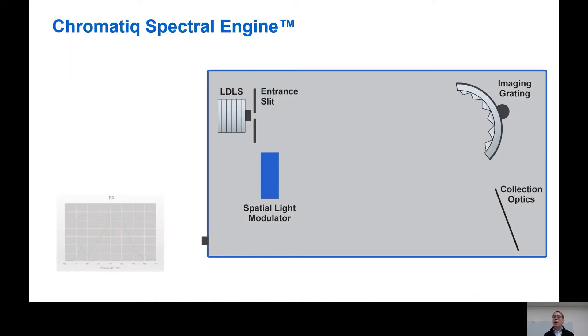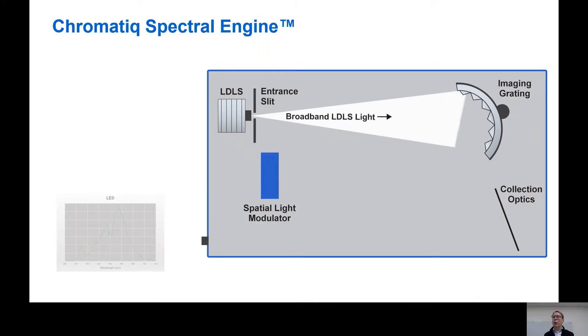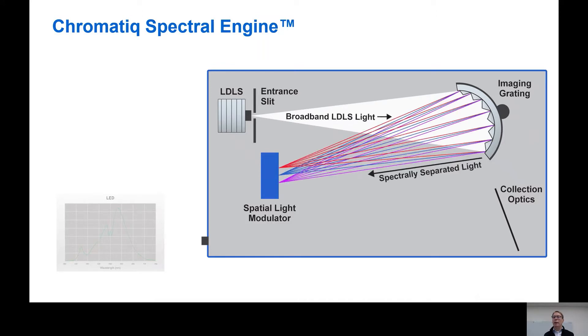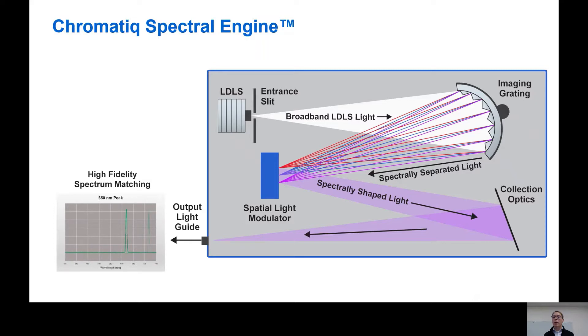The system is built around the high radiance of the Energetic Laser Driven Light Source, or LDLS. Broadband light from the LDLS is first separated by wavelength by the imaging grating. Then the light is shaped to accurately match the desired spectrum. The output can be switched from one spectrum to another very quickly within 100 milliseconds with no settling time.